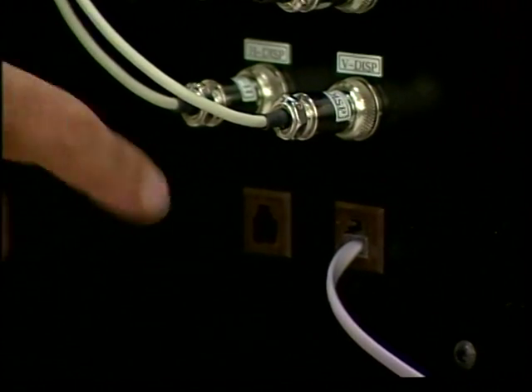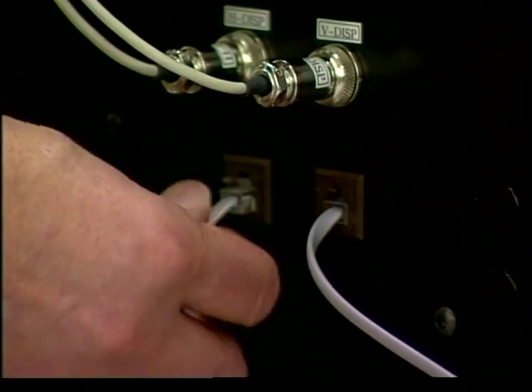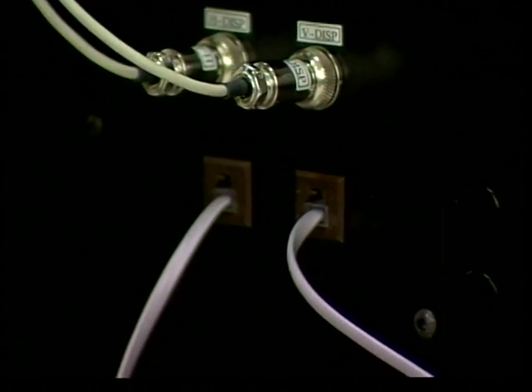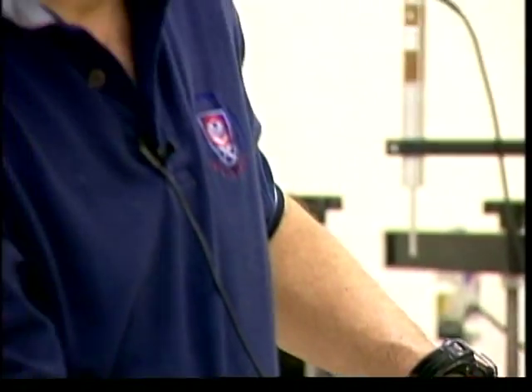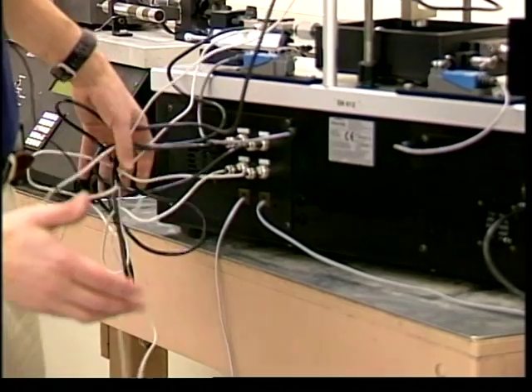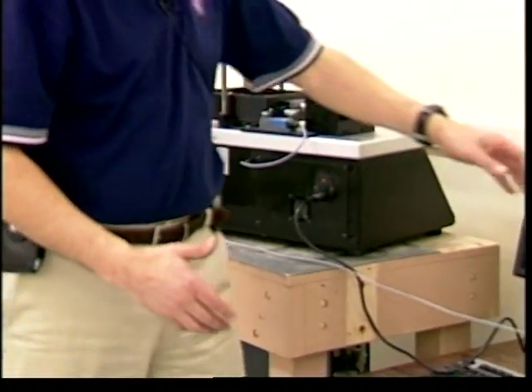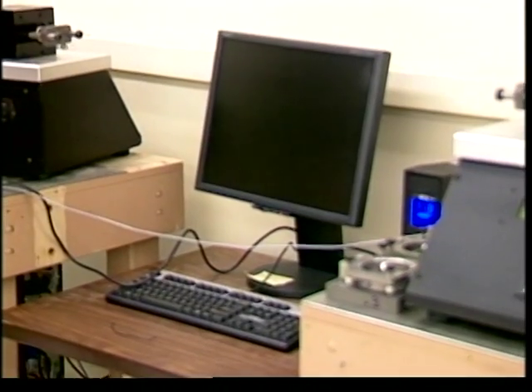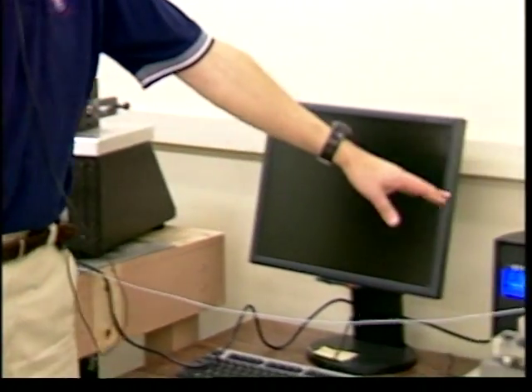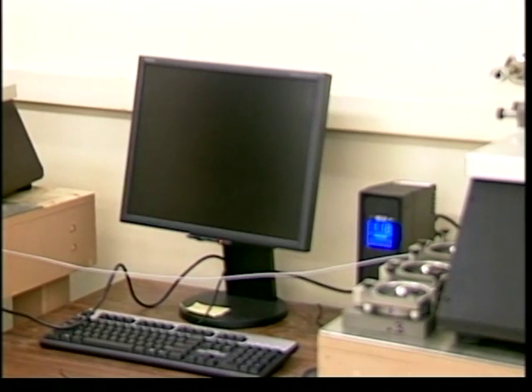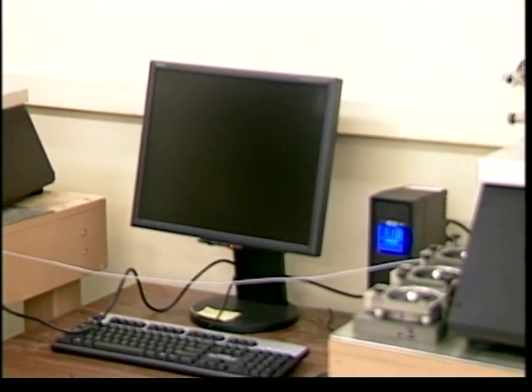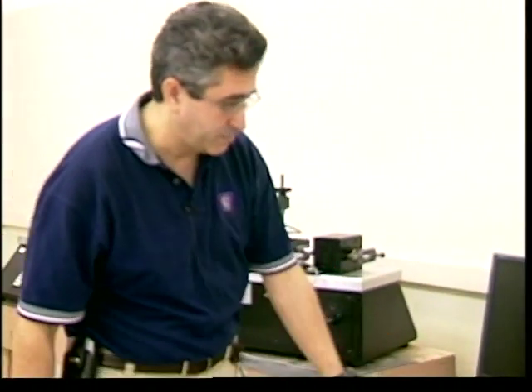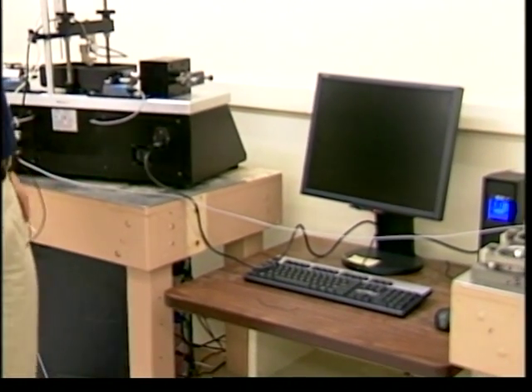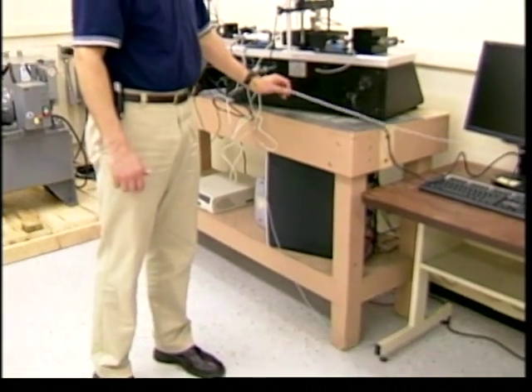There's only one power cord that plugs in, and there is a network communication between the different units, or if you only have one unit, you'll have a network communication cable that goes to the PC, and this port will have the terminator in it. So if you have multiple units, then you're going to daisy chain them. Otherwise, you're going to have a terminator here if you only have one direct shear unit. So this is for the power and the data communication with the PC. Again, we highly recommend that you connect the power to a UPS system, which will provide backup and also clean up the electrical power supply. So that's the UPS. This is your PC here. There's a network communication card inside the PC that is connected to the cable.